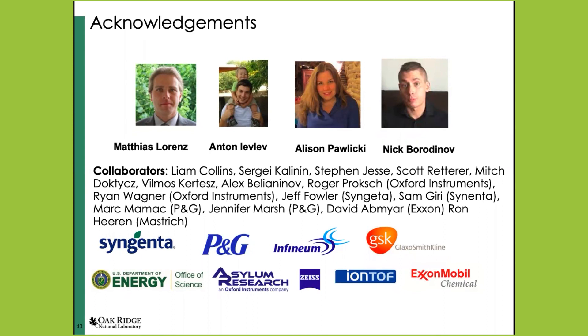The Asylum Research AFM has really been great — it's a very low noise system. We have an encasing around it that minimizes noise, with a panel on the side that allowed the extraction tube to go through, minimizing noise coming in from the mass spectrometer system. The system itself also sits on an active-passive damping system — we have active vibration isolation for the vibrations that are coupling from the mass spectrometer.